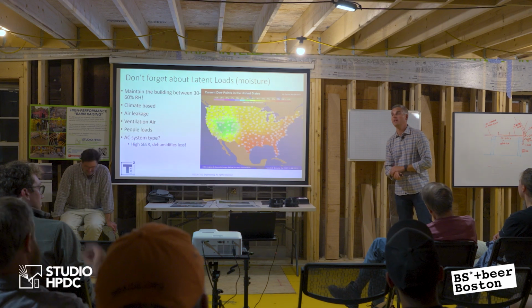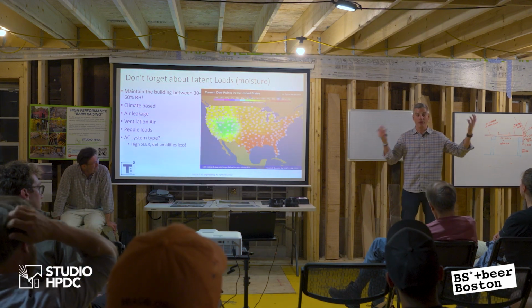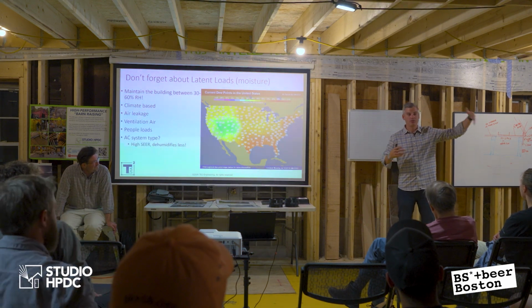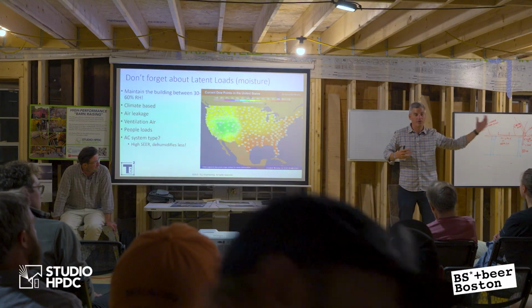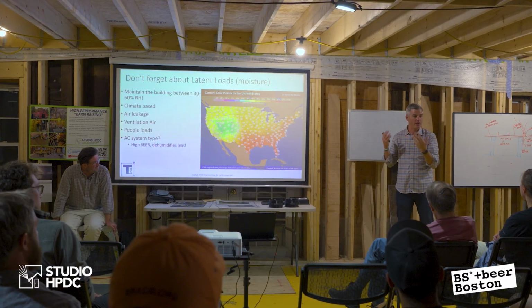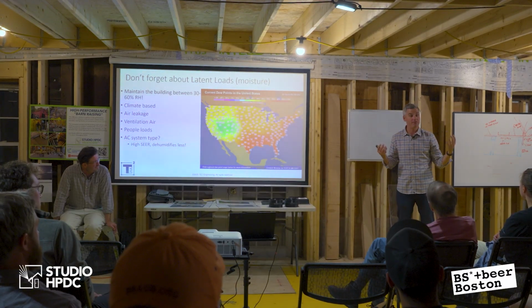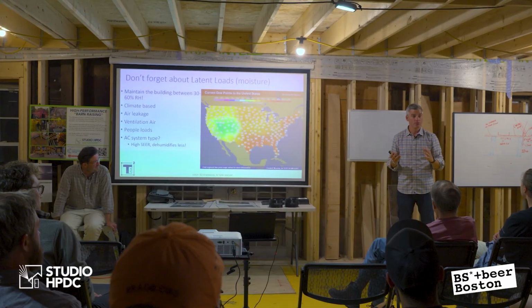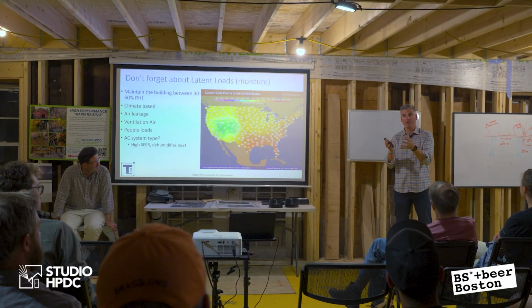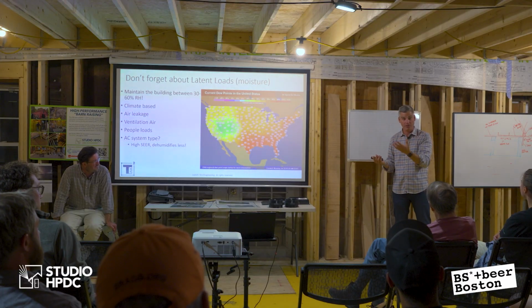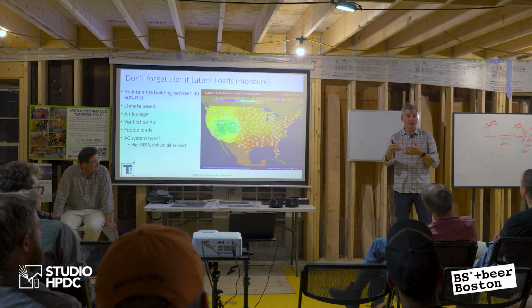Yeah, so if you look at a traditional ERV, and let's say we're here in Boston, outdoor temperature is, let's say, 12, 13 degrees or even colder, 5 degrees. The discharge air coming off of a high efficiency ERV is going to be somewhere in the 50 to 55 degree range. So that 50 to 55 degree supply air coming off the ERV does need some post conditioning, because if you blew 50 degree air on somebody in the wintertime, it's going to feel really cold. So the idea of post treating it is a real thing.